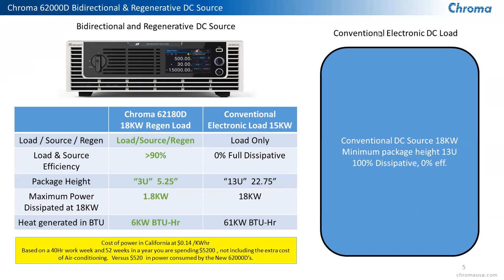This unit, because of the efficiency, we can package it into a 3U package, 5.25-inch height. And with the conventional 15 kilowatt, the minimum is typically around a 13U or 22.75 inches. Again, the maximum power consumed and dissipated by the 62000D family of products would be only less than 1/10 of the total power. So at this unit at 18 kilowatts, you're only going to dissipate 1.8 kilowatts of power versus a conventional load that's going to dissipate the full 18 kilowatts. And that also reduces the heat generated in your facility.